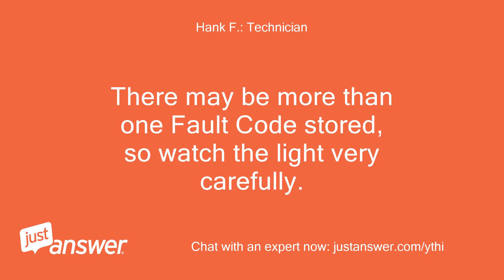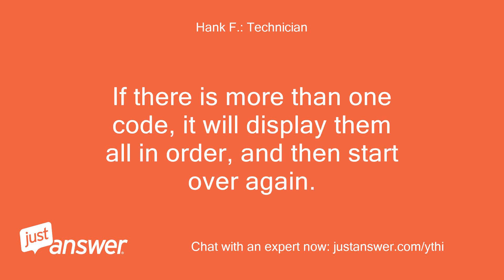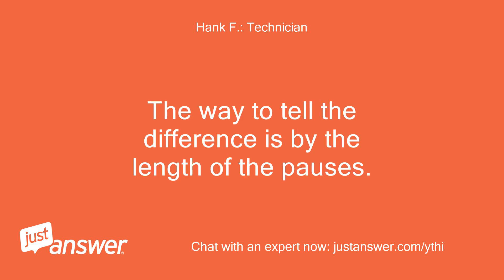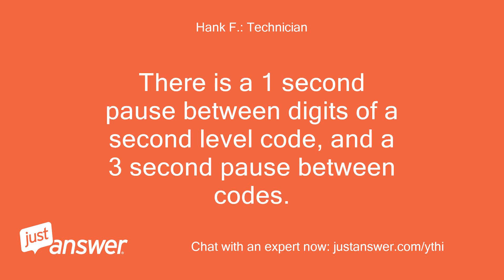There may be more than one fault code stored, so watch the light very carefully. If there is more than one code, it will display them all in order and then start over again. Be very careful not to misread a first-level fault code (single-digit code) as a second-level fault code (double-digit code). The way to tell the difference is by the length of the pauses. There is a 1 second pause between digits of a second-level code and a 3 second pause between codes.